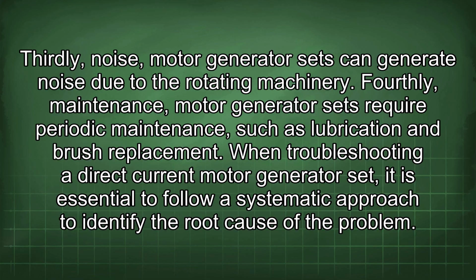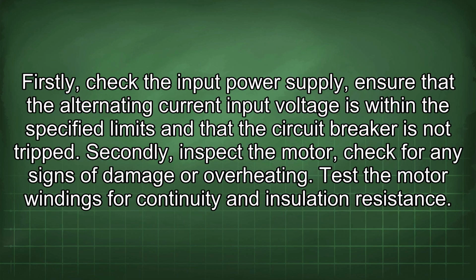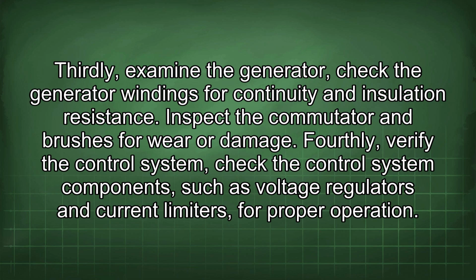When troubleshooting a direct current motor generator set, it is essential to follow a systematic approach to identify the root cause of the problem. Firstly, check the input power supply. Ensure that the alternating current input voltage is within the specified limits and that the circuit breaker is not tripped. Secondly, inspect the motor. Check for any signs of damage or overheating. Test the motor windings for continuity and insulation resistance. Thirdly, examine the generator. Check the generator windings for continuity and insulation resistance. Inspect the commutator and brushes for wear or damage.